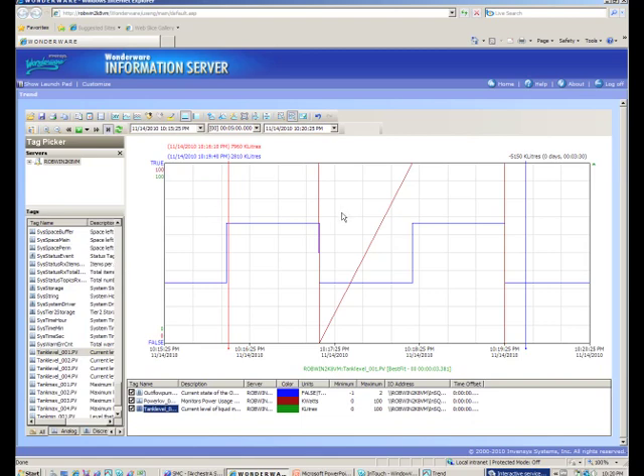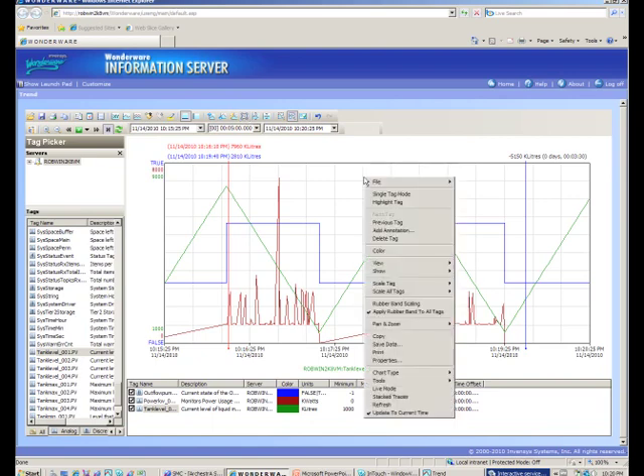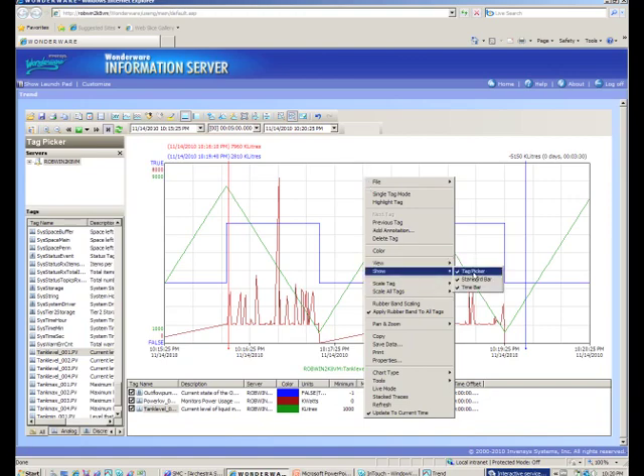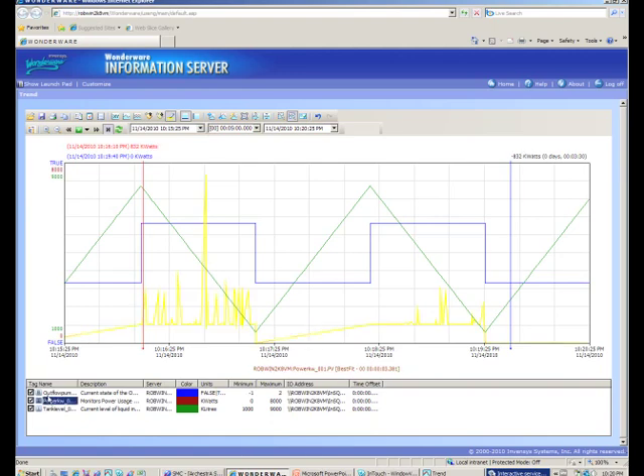As you can see the trend needs to be scaled so we'll scale it and we can now see all of our information. If I right click on the trend and say don't show me the tag picker any longer it'll give us more space to work with but as we'll see when we save the trend unfortunately when we reopen it the tag picker will once again reappear. So I'm going to turn highlighting on and for example since power is what we're most interested in I'm going to click on the power kW tag and you'll see it instantly turns yellow.